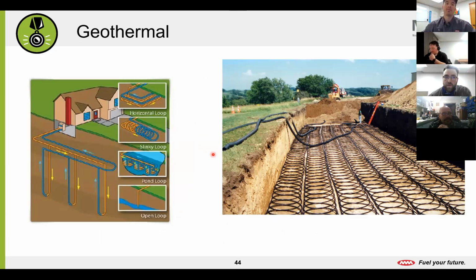So I'll move on to another type of hydronic heating and cooling, and that's geothermal. I personally haven't really worked on much geothermal, but the principle is essentially that the earth is going to stay a relatively constant temperature, and we can run water through that to reject or absorb heat. You can see some of the different types here, and it's not my expertise, but essentially you have to take into account the space, how much land do you have? You see this big trough they dug to lay down a bunch of water lines. Sometimes they'll bore and go straight down a long ways. In this one, they have a pond, or you'll see people that have a stream and they'll run their water lines through there. Just a spot where you have a constant source of energy to either pull from or reject to.